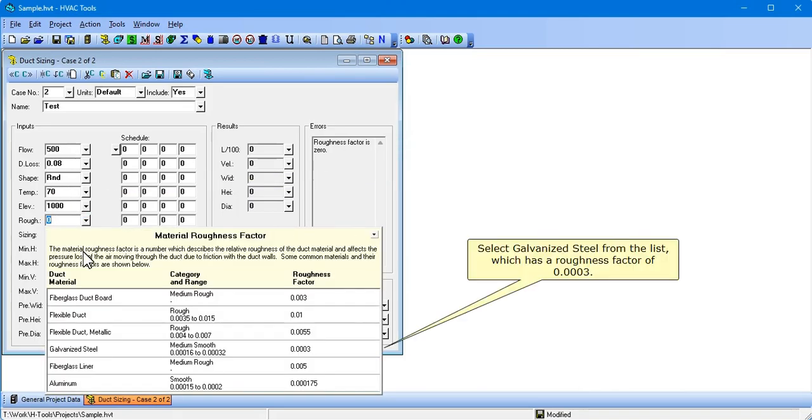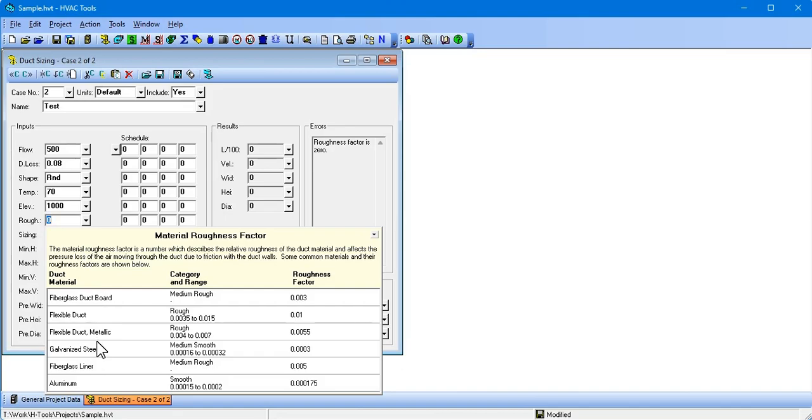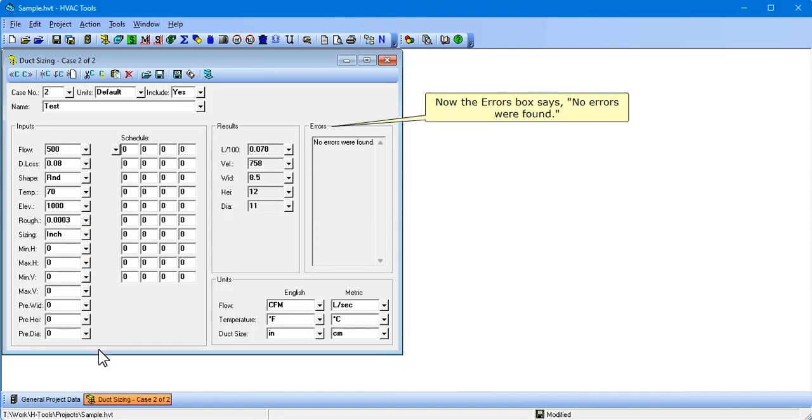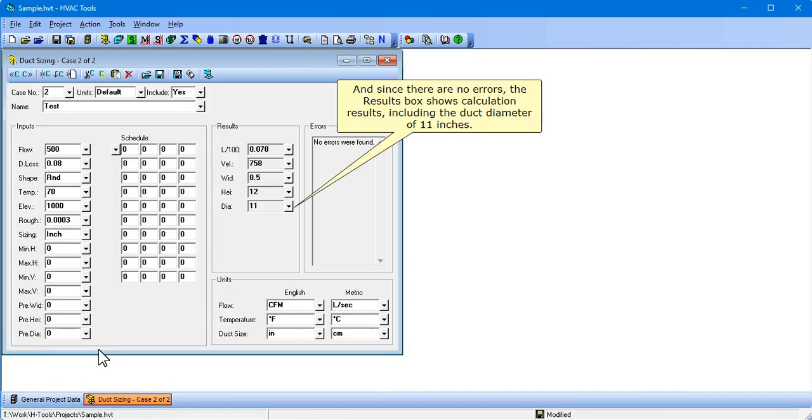Select Galvanized Steel from the list, which has a roughness factor of 0.0003. Now the Errors box says no errors were found. And since there are no errors, the Results box shows calculation results, including the duct diameter of 11 inches.